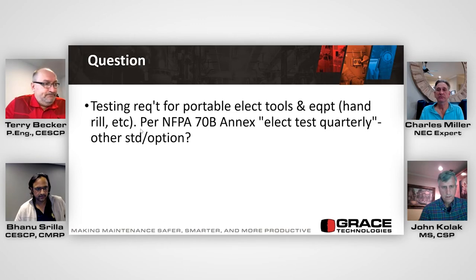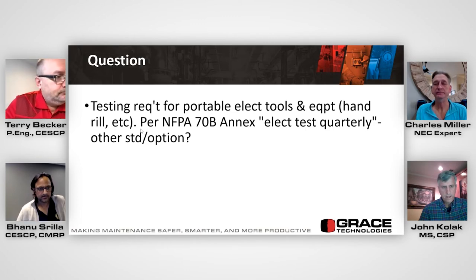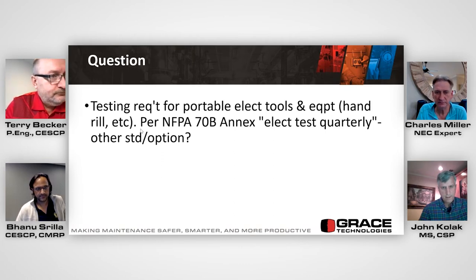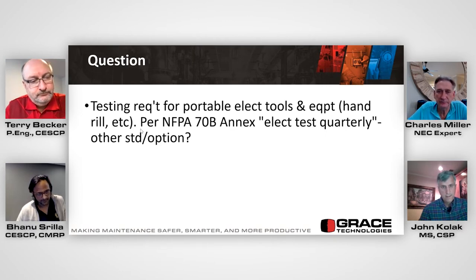A portable electrical tool, single phase now, will require GFCI protection, so if there's any testing associated with the GFCI, that's all right. But otherwise, this, by the way, made a 50% reduction in shock injuries. It made a huge difference to have that. Basically, the GFCI normally doesn't need testing unless the manufacturer says it does.